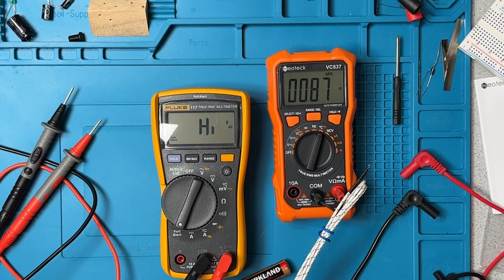In terms of temperature reading, the Neoteck is about the same level of accuracy as pretty much every other multimeter I've used with one of these thermocouples. They seem to be calibrated in that little range, and in my experience they read about 3 or 4 degrees Celsius high.